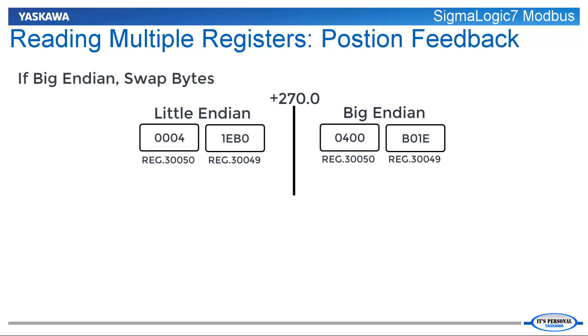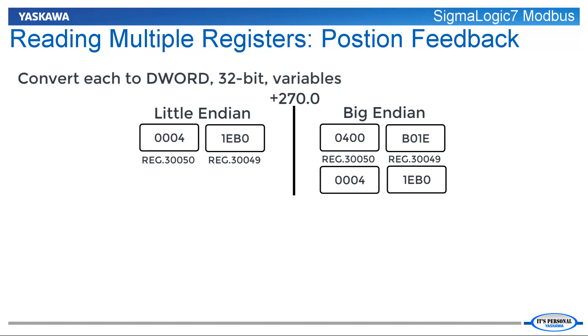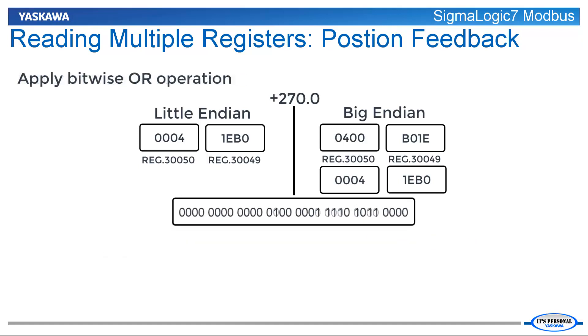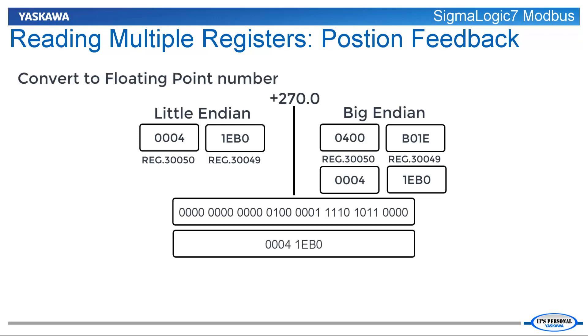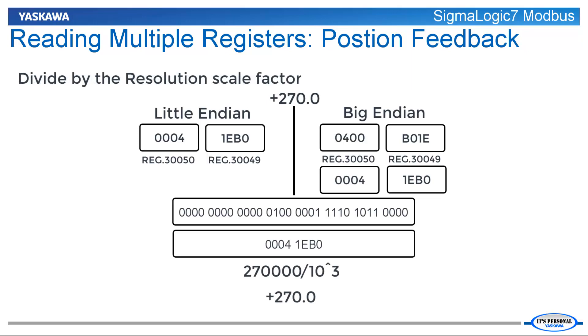First, if the controller stores the data in big-endian format, swap the bytes within both words to interpret the number correctly. Next, read both 16-bit registers into separate 32-bit variables, then shift the data in the high word 16 bits to the left. Apply a bitwise OR to combine the two registers into a single 32-bit number, then convert that value to a floating point number and divide by the resolution scale factor.